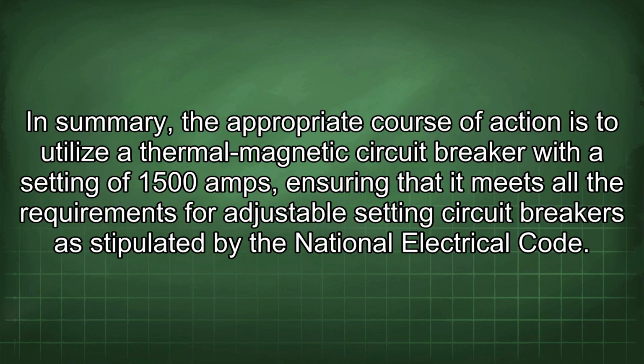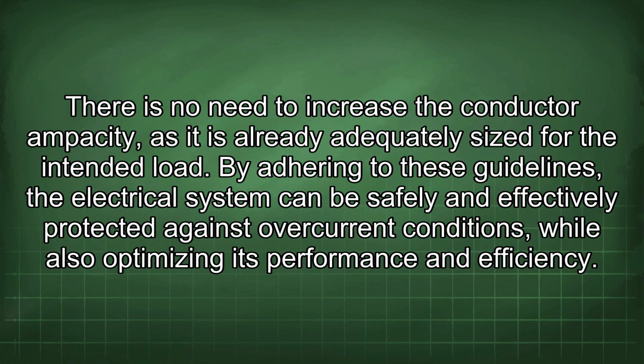In summary, the appropriate course of action is to utilize a thermal magnetic circuit breaker with a setting of 1500 amps, ensuring that it meets all the requirements for adjustable setting circuit breakers as stipulated by the National Electrical Code. There is no need to increase the conductor ampacity, as it is already adequately sized for the intended load. By adhering to these guidelines, the electrical system can be safely and effectively protected against overcurrent conditions, while also optimizing its performance and efficiency.